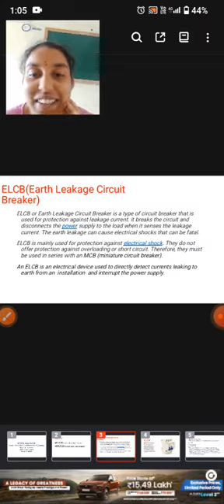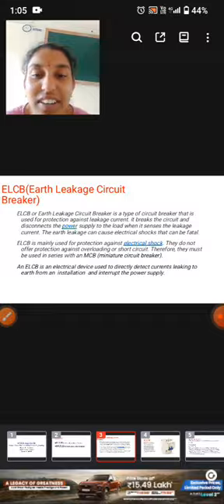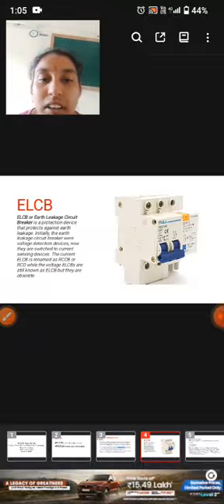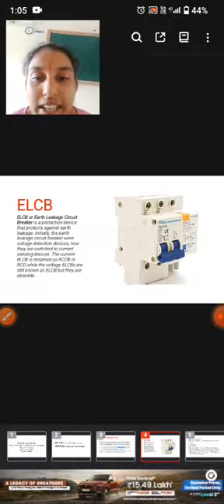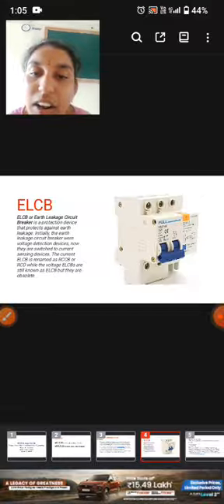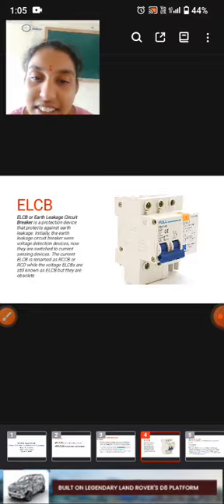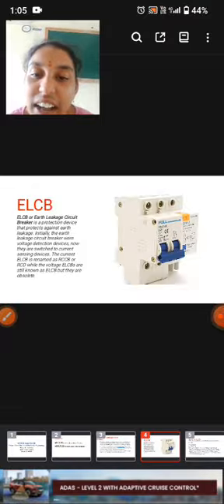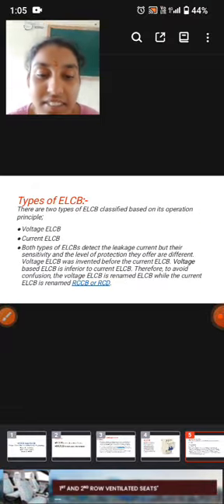An ELCB is an electrical device used to directly detect currents leaking to earth from an installation and interrupt the power supply. This is the device of ELCB. It is a protective device that protects against earth leakage. Initially, the earth leakage breakers were voltage detection devices. Now they have switched to current sensing devices.